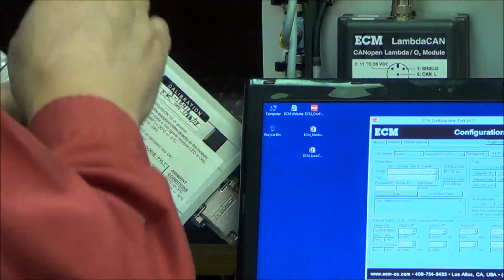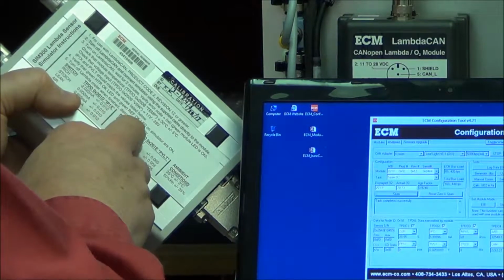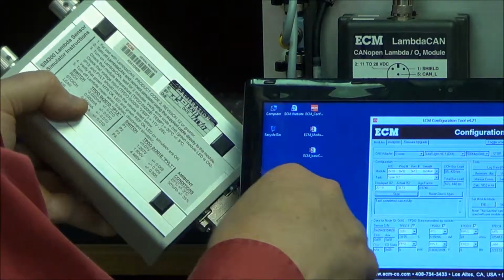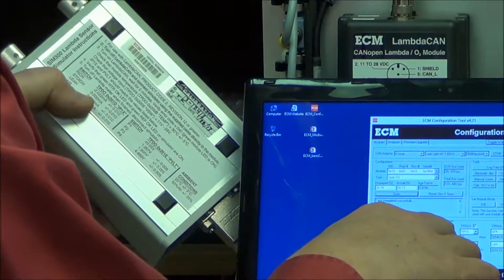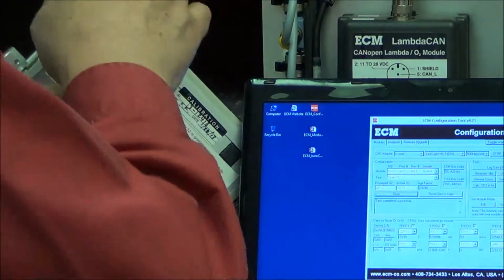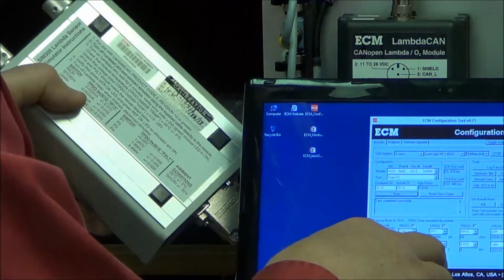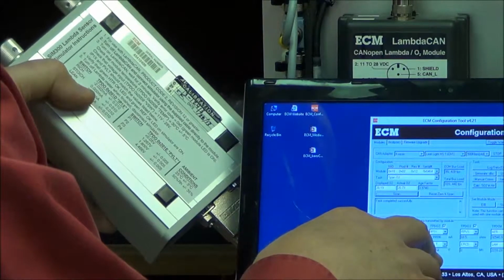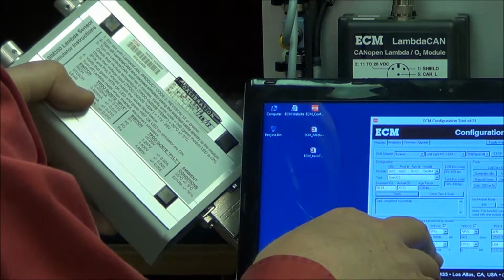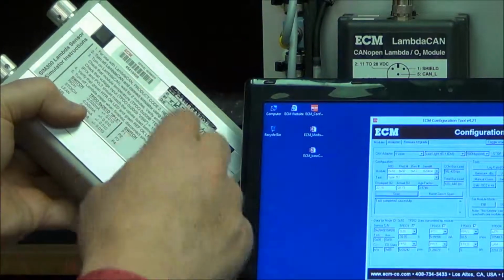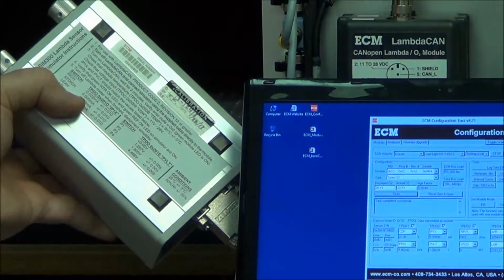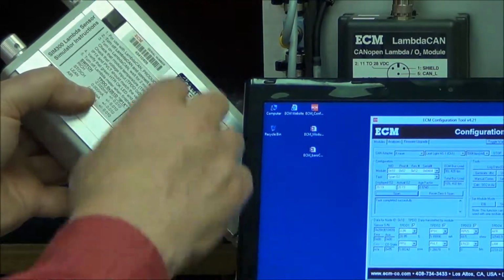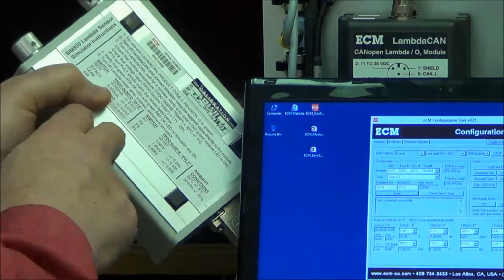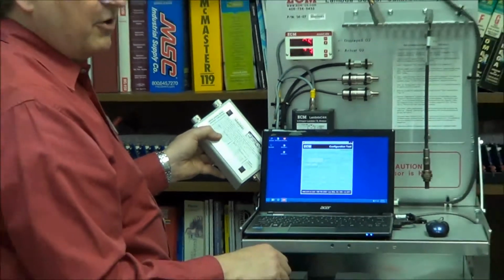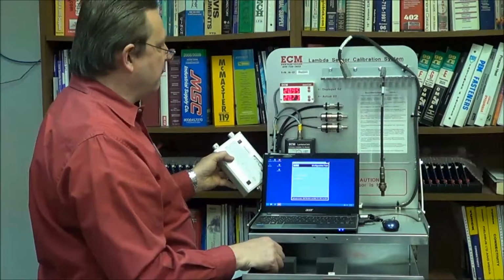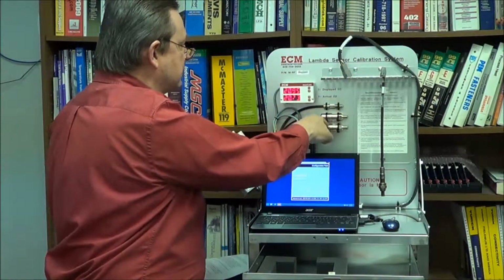To simulate pressure outputs, it's voltage, you have 4 voltages. The first one is less than 5 millivolts, and that is called PVLT, the pressure voltage. This thing is 8 millivolts. Then you go up to 1.267. It's a little bit of averaging going on here. Okay, it's coming in. 1.266. It's within spec. And you have 2 more voltages to go through. Once the LambdaCAN has passed this test, you know that it can accurately measure the currents and voltages from the Lambda sensor and the pressure sensor.